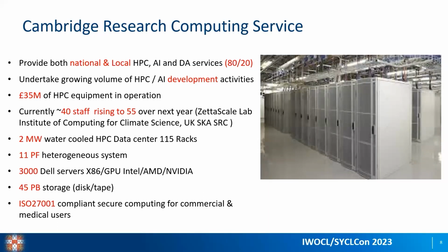Now if you're buying new servers, the processors in those servers are getting hotter and hotter. It's the only way the IT industry can keep the ball rolling and give us more power per server. They have to make the silicon bigger and more hungry, and someone worked out that they could keep making it hotter if they put water directly on the chip. So now we're having water-cooled chips. Before water cooling, if you wanted a dense form factor, a chip was limited to around 200 to 240 watts. Now with water cooling, in x86 servers we're up at 350 watts. Your GPUs are going to be up at 600-700 watts, and it's going to keep going up.